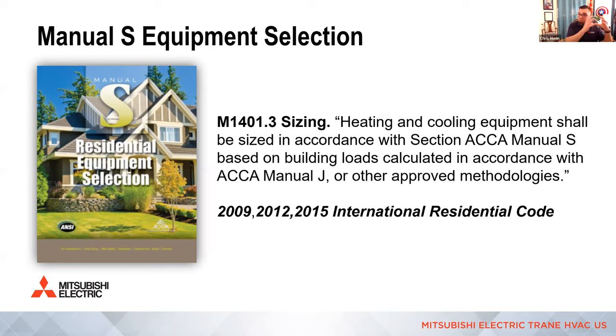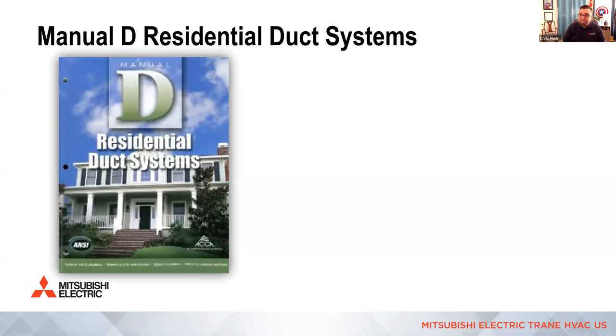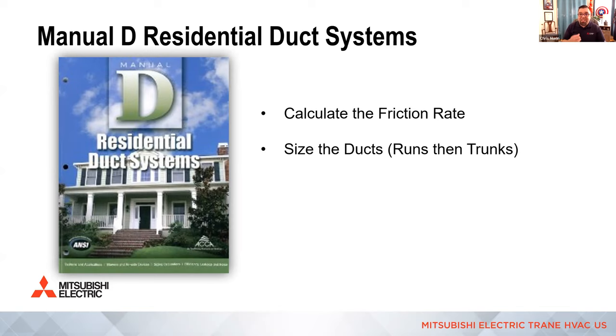So once you know what's needed for the building, you select the right piece of equipment. If it's ducted, then we get to Manual D. So it goes J, S, then D. This is the third part of that design pie. And in Manual D, what we do is calculate the friction rate we need, which I'm going to walk you through today. We're going to size the ducts.